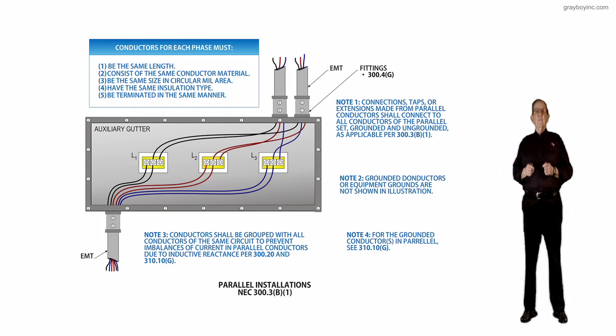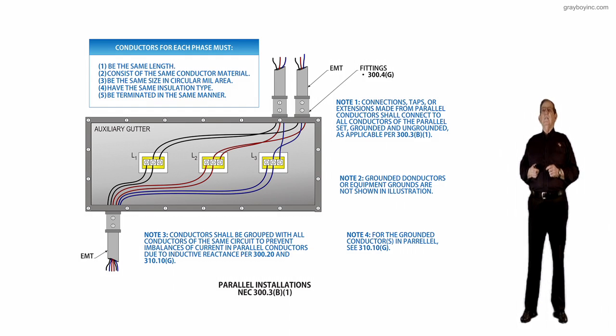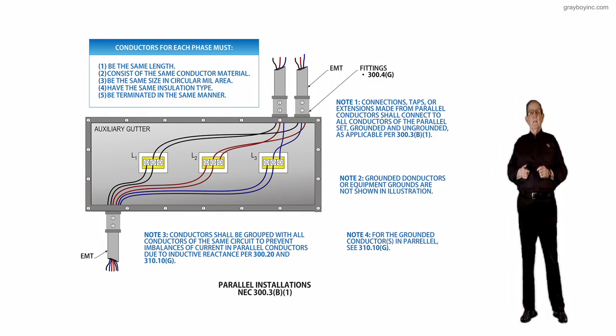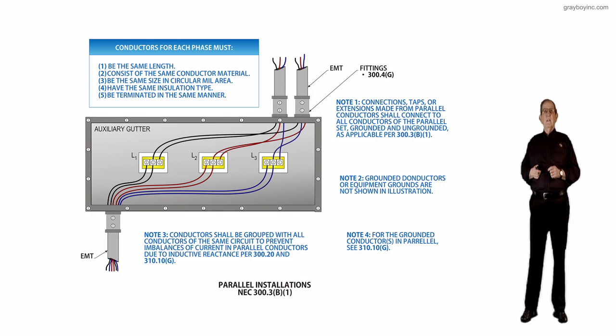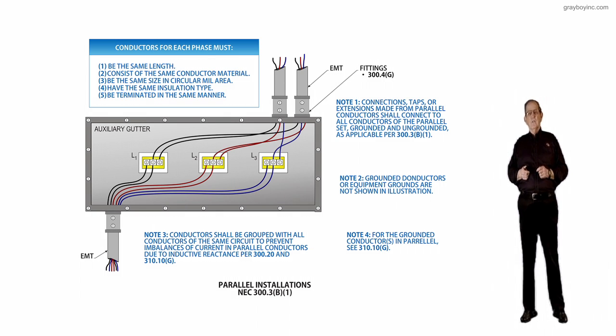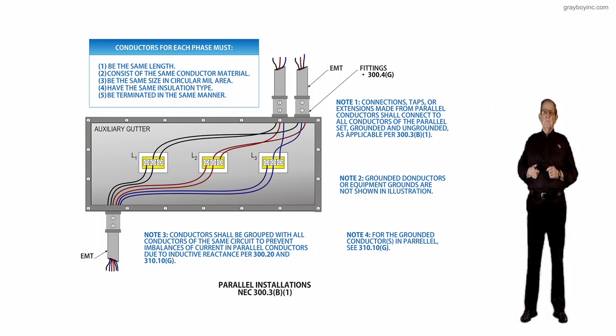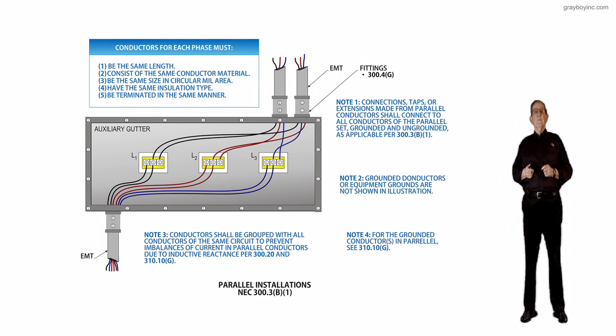If you look at the paralleling section number, 310.10G deals with paralleling conductors, and they have to be at least 1/0 AWG or larger for reasons we previously mentioned.